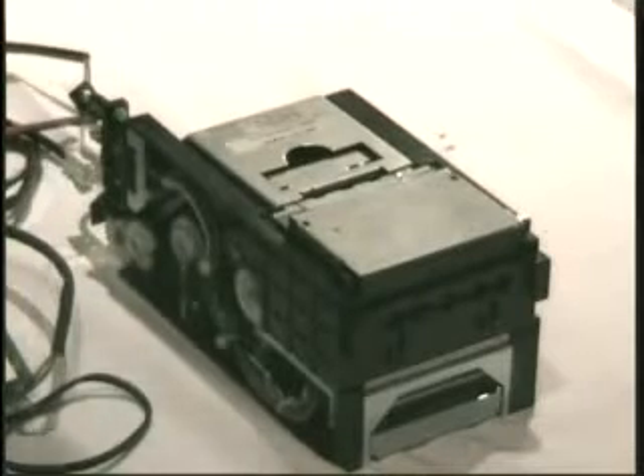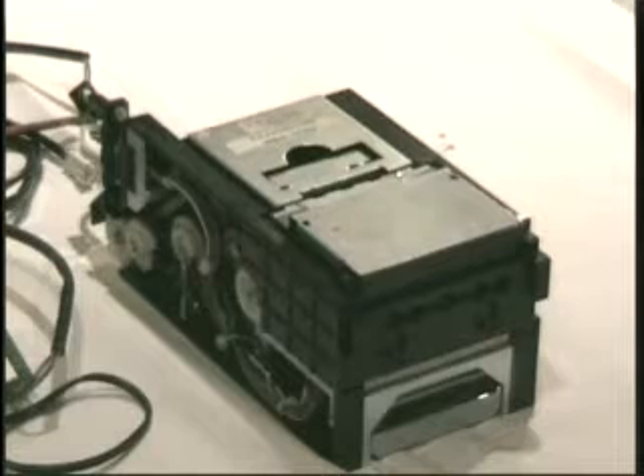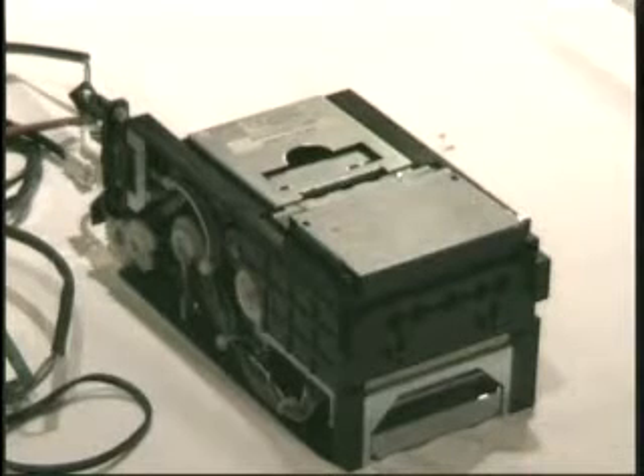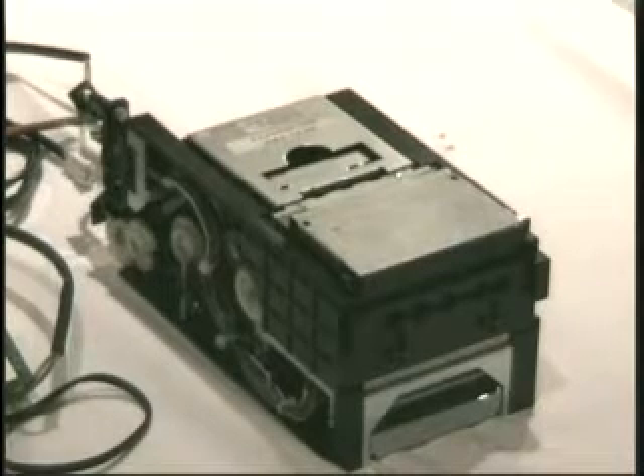Okay, for diagnostics, if it is having a problem that you can't fix with a quick cleaning calibration, there's a bunch of diagnostic tests we have in there. I can't remember which page it's on, but it should say test modes and have a big chart on it. Page 7, thank you. All of the diagnostics start by putting dip switch number 8 on.